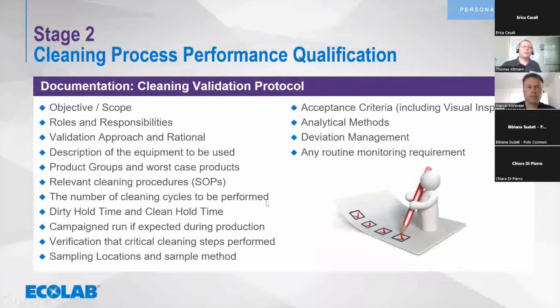So from our point of view, the documentation goes even more into the documentation of how long is the cleaning hold time, how long is the dirty hold time, what kind of campaign is running before the cleaning starts, what is the worst case in that case, and I will also demonstrate during stage two what sampling locations I will use to identify my acceptance criteria. And I will also describe how I do deviation management. If I find something strange, if there is a deviation, do I have to redo everything? Do I just re-clean something? So this is what we will identify during stage two.